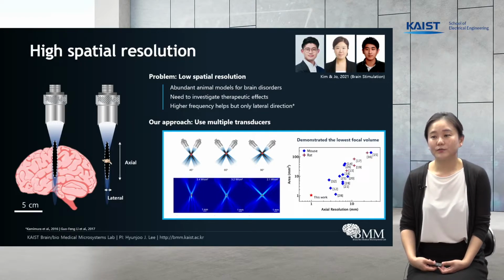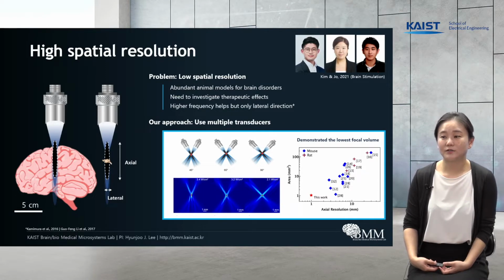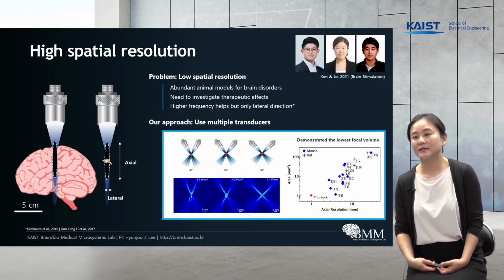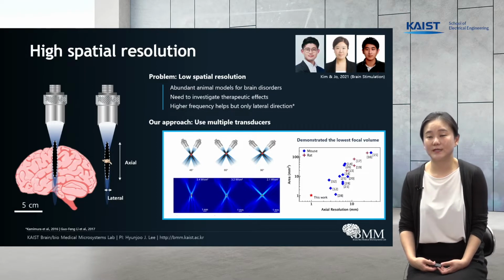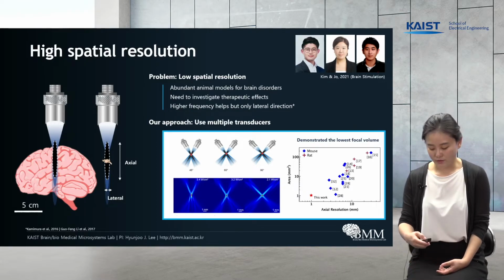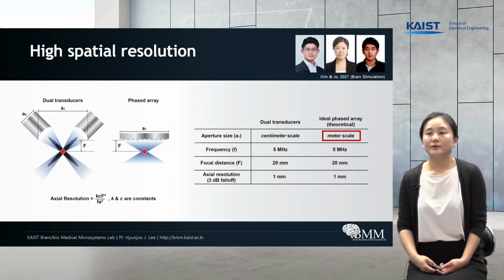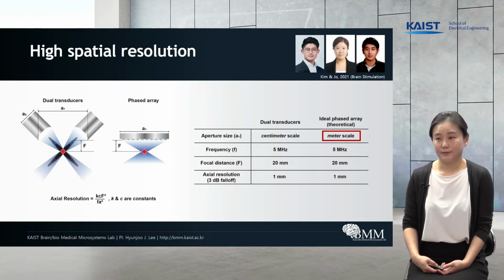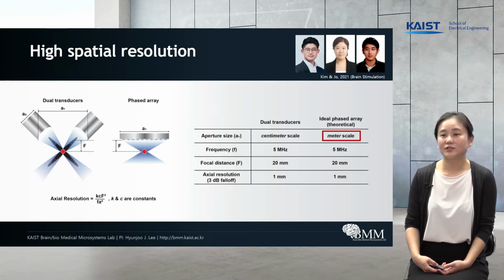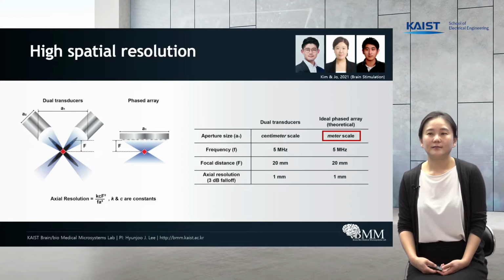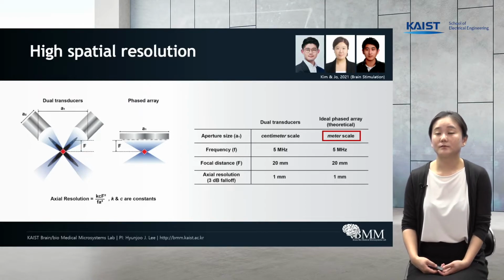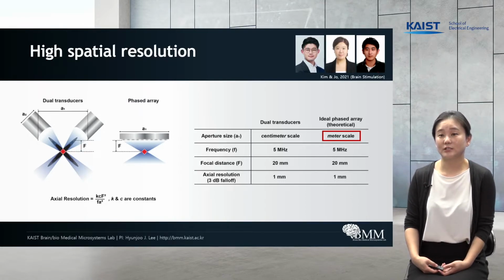Among all the ultrasound neuromodulation work on mice and rats, you can see that our work shows the lowest axial and lateral resolution. Although this technique seems fairly simple, there is a clear advantage of this system versus the phased array focusing technique, in that the aperture, the size of the transducer, becomes extremely large in order to achieve the same spatial resolution achieved by our dual transducer technique.